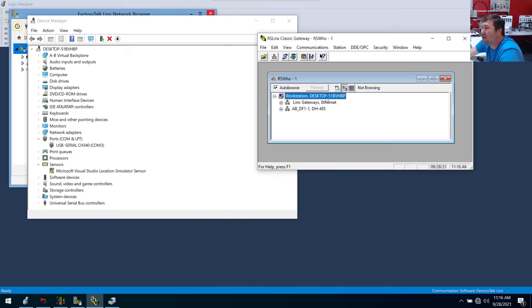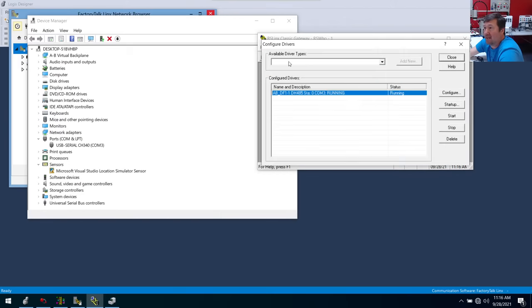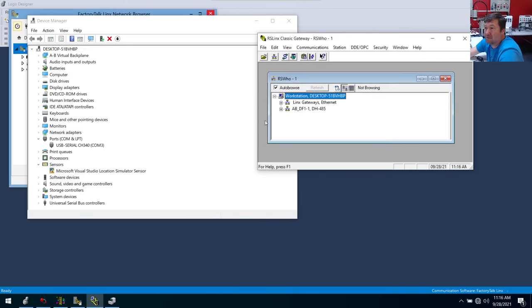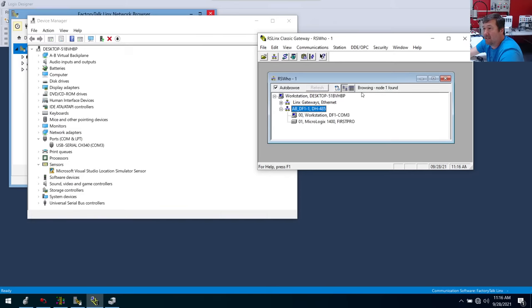Instead of going right into our PLC software, we can go to Communications in RS Who, and here we can see which PLCs are actually out there. By default the only thing that's there is this RSLinx gateway — gateway's almost going to do you no good when you're trying to communicate with PLCs, so if you see it, just don't even click on it. We're going to click on this ABDF1, and there you go — now we have a MicroLogix 1400. This is the processor name — we know we have a MicroLogix 1400, and its processor name is FirstPro.